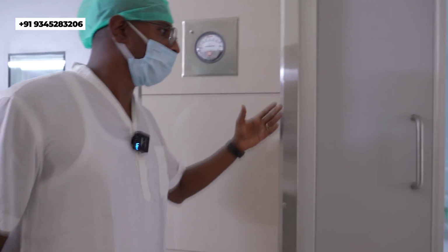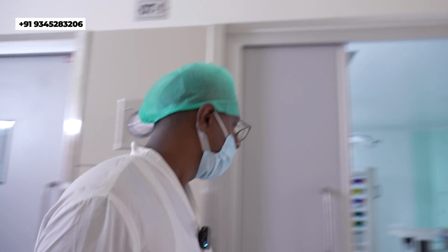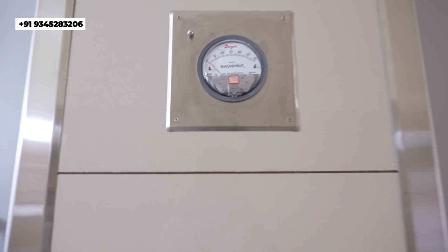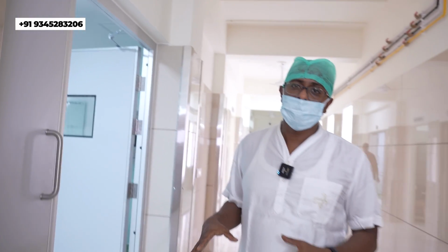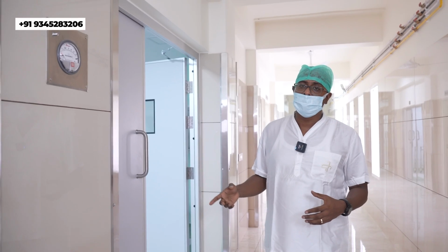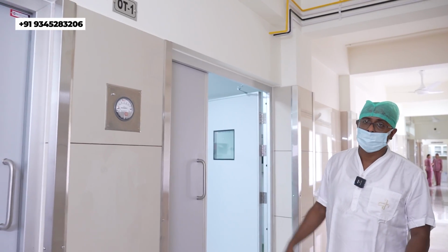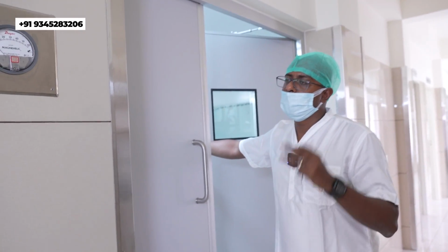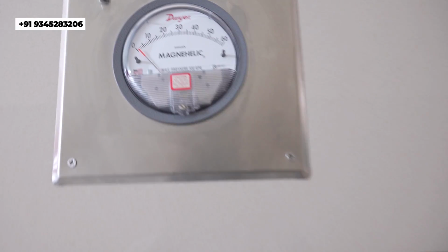So come, let's go inside the andrology OT. This is the pressure gauge we kept outside, because for this OT we need to see all the pressures from outside - it's a mandatory requirement, so we kept it outside. We check the purity of the filters, since air is purified only through the filters.